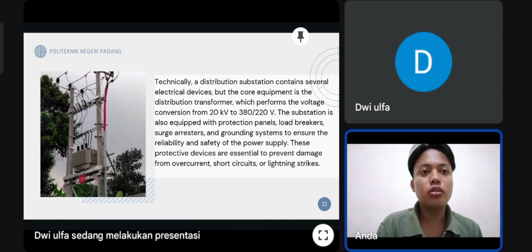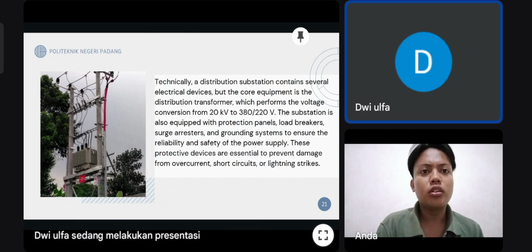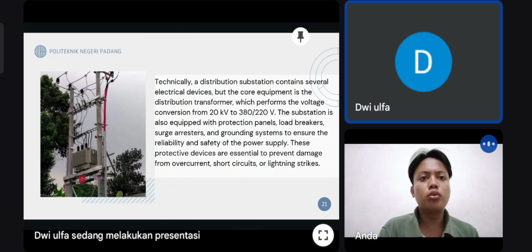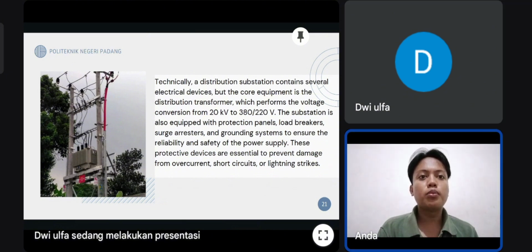Distribution substation contains several electrical devices, but the core equipment is the distribution transformer, which performs the voltage conversion from 20 kV to 380/220 volt. The substation is also equipped with protection panel, load breaker, surge arrestor, and grounding system to ensure the reliability and safety of the power supply. The protection devices are essential to prevent damage from overcurrent, short circuit, or lightning strike.